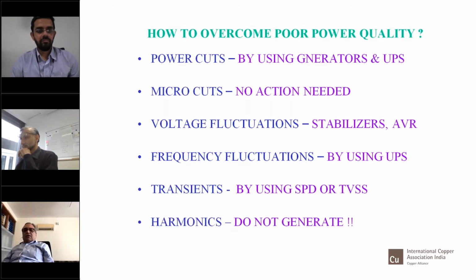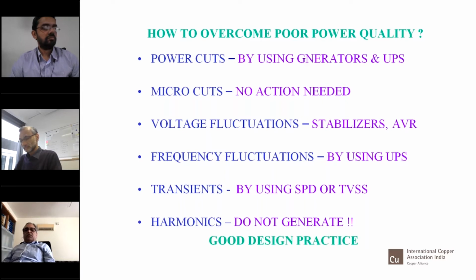The last thing is harmonics, which I will assign a large part of my talk to. Harmonics are not being supplied by the utility company, although some producers generate them and they travel to us via utility companies. Most harmonics are actually produced by consumers, and then have to be managed and mitigated by the consumers. Very soon, electricity distribution companies will start penalizing for injecting harmonics into their system.